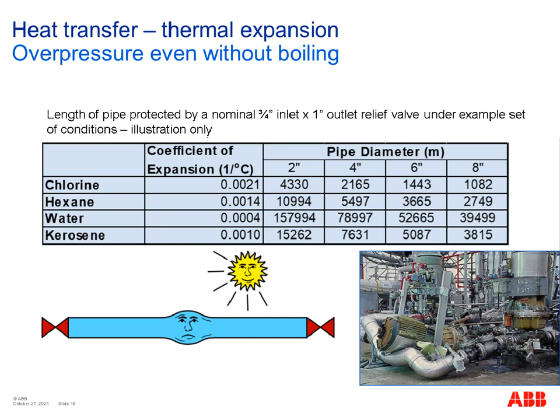So with water, with the smallest coefficient of expansion of those 4, with a 2-inch line, you could protect 158 kilometers of pipe work, and with an 8-inch line, you could still protect almost 40 kilometers of pipe work. So a very, very long length of piping. With chlorine, with the higher coefficient of expansion, it's not as much as that, but still with a 2-inch line, it's over 4 kilometers you could protect. And with an 8-inch line, it's still over 1 kilometer you could protect. So that just shows that although thermal expansion could rupture a line, you can protect a lot of length of line with just a small basic thermal relief valve.